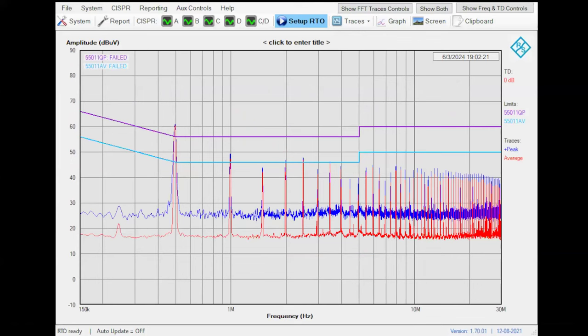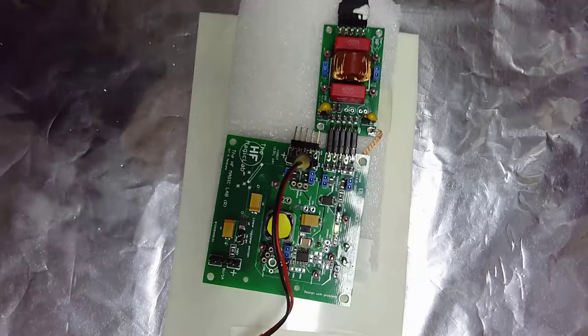You have the possibility to use an external device that is called LISN, or is working with transformer, resistors. There is different methods to do that. But what I like to do many times is to work with the oscilloscope. So let me show you how is the setup of my instrument here.